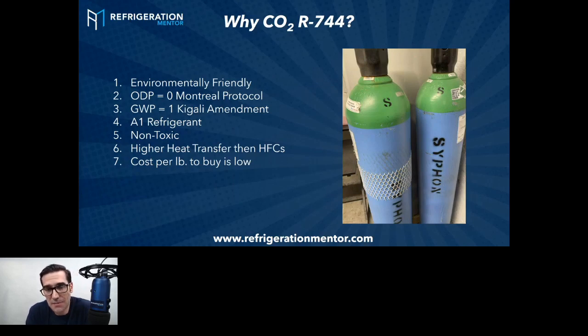Back in the 80s, something was called the Montreal Protocol. Some of you may have heard of it, may have not. Basically, these were refrigerant gases that had chlorine in them, so CFCs. What happened is they would start to make a hole in the ozone layer. Scientists saw this, and then there was a phase down and phase out of those. This happened a long, long time ago, so a bunch of refrigerants like R12 and R502 started to get delisted and phased out.